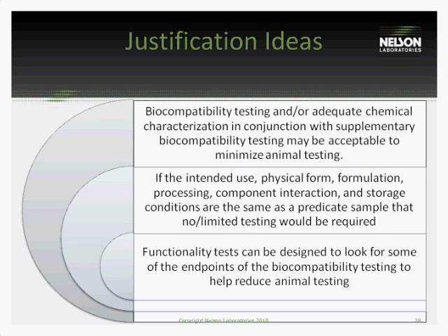And this one also kind of makes me smile, not because I'm thinking that this is going to be great for actual submissions, but a lot of times my clients call in and say, I have a device that's the same material as my competitor's device, and they have a 510(k), so I'm not going to do any biocompatibility. That's not where that stops. If you look through these checkpoints, there's a lot of things you have to consider when you're saying no biocompatibility is required based on predicate or other use. So these are some of the checkpoints you have to look through to make that assessment.